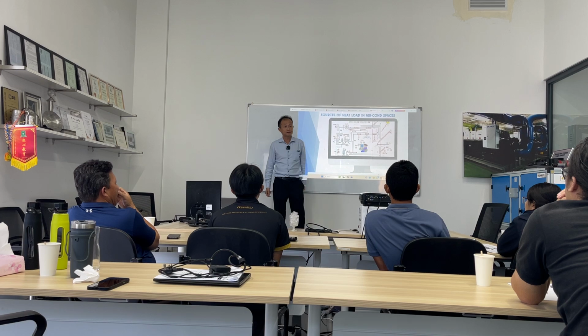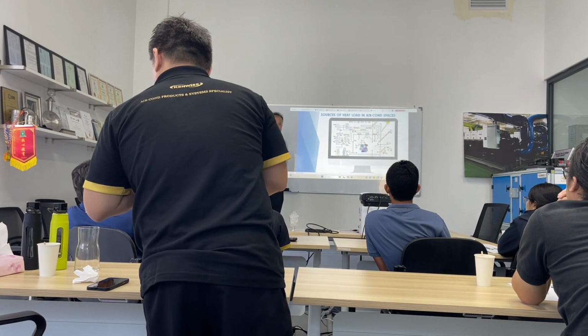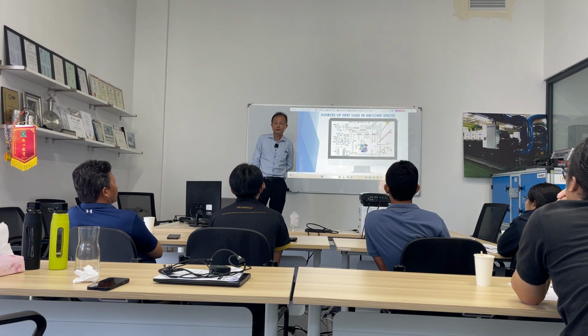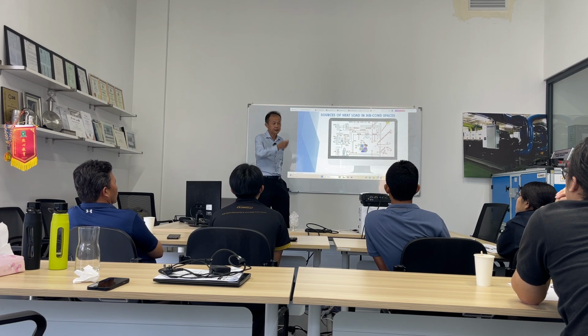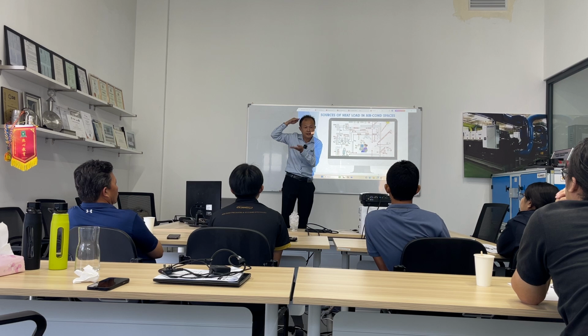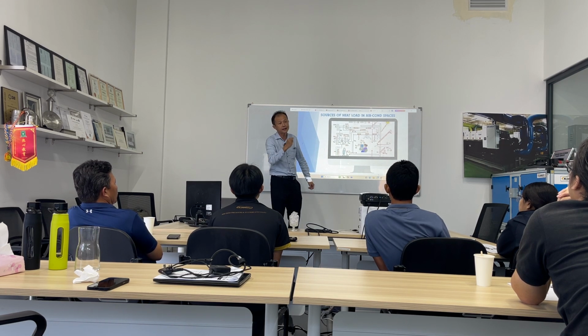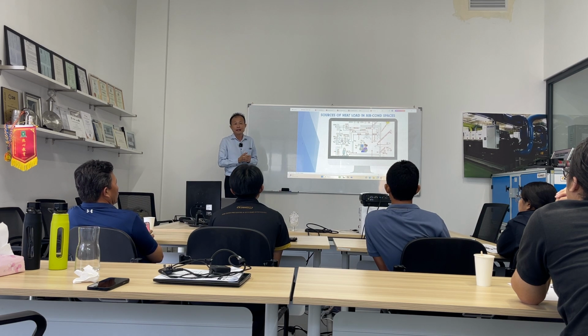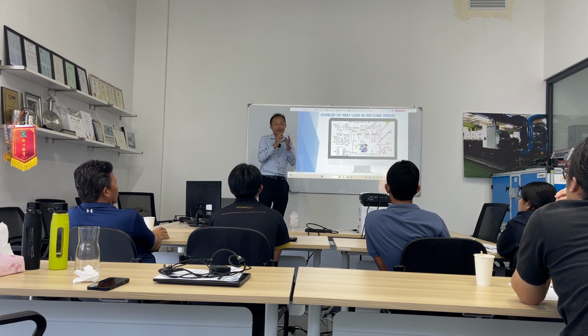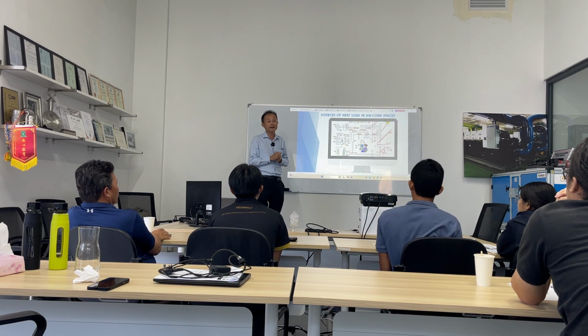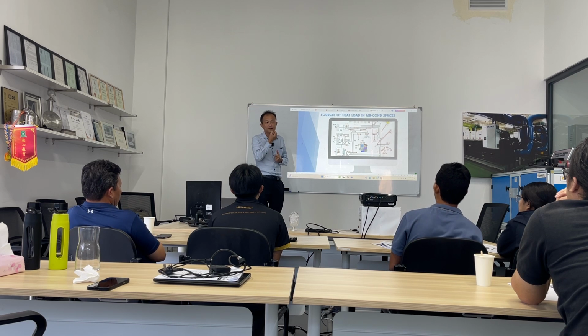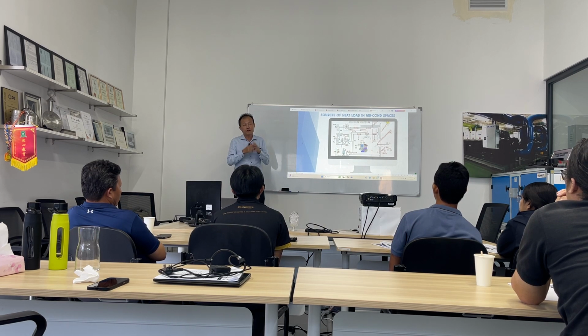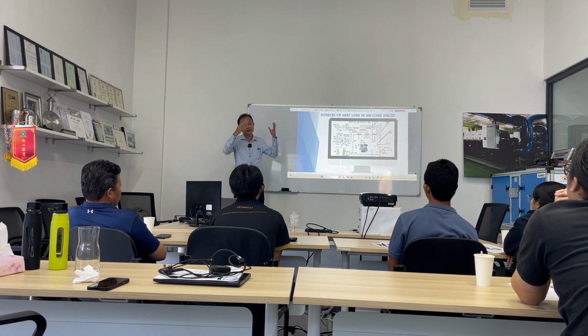Another load is your human body. Your human body is a very substantial component of the heat load in the aircon space. Your body generates two types of heat. One is sensible heat: the heat that you can measure with a thermometer and see the temperature rise. You can sense it. Another is latent heat. Latent heat is the type of heat caused by the moisture content inside the air. The vapor coming out from your body creates a latent load, which affects the humidity, or the relative humidity level, inside the space.